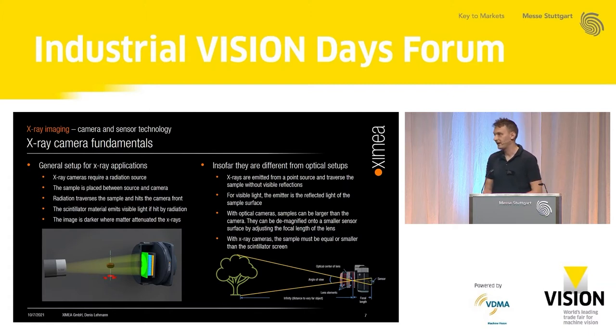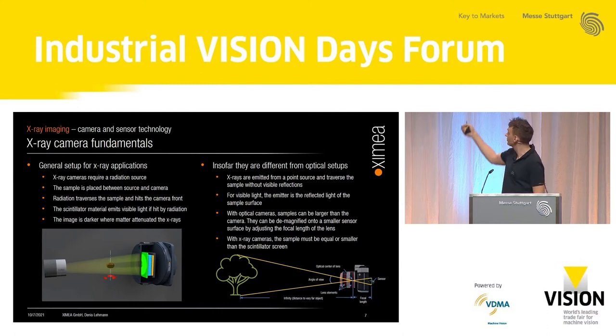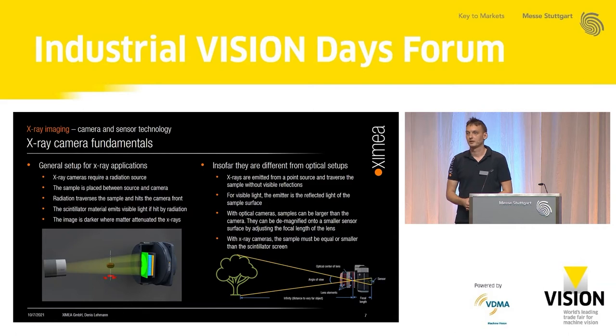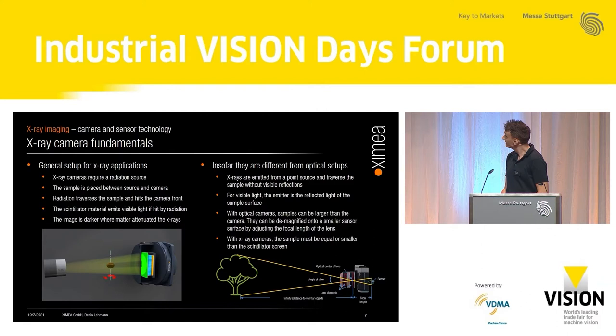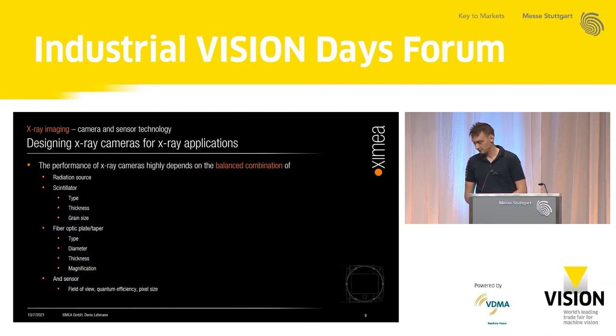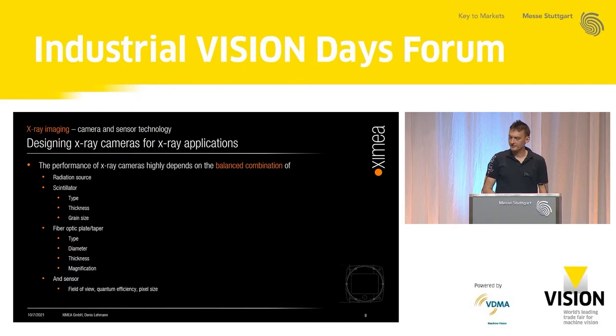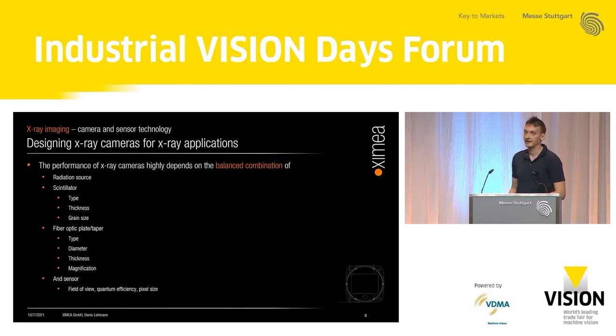For optical setups, the reflected light from large objects is demagnified onto the sensor surface simply by changing the focal length of your lens. For X-ray cameras, there is no lens. That means the sample must be equal to or smaller than the size of your field of view or scintillator screen. Every X-ray camera is different and usually customized to a specific application. Performance highly depends on the balanced combination of the radiation source, scintillator, fiber optic plate, and sensor.